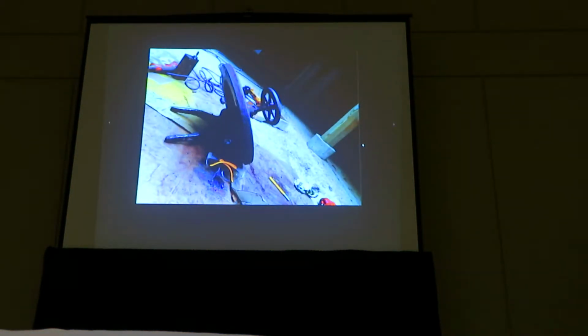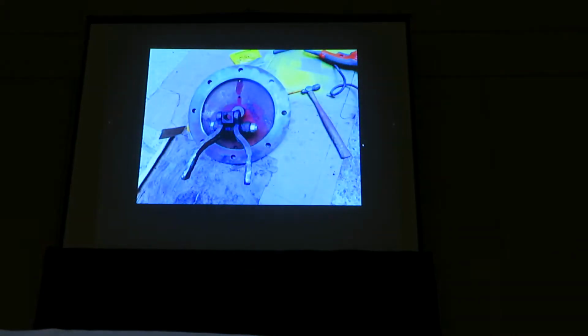And while Phil unjammed the valve with heat and picked all the dirt and crud out of it, I successfully repaired the broken valve arms and other cast iron pieces inside it with silver solder at a temperature of approximately 2,000 degrees. This was all done at home. I took the entire valve bonnet home with me and got it working properly and all clean.